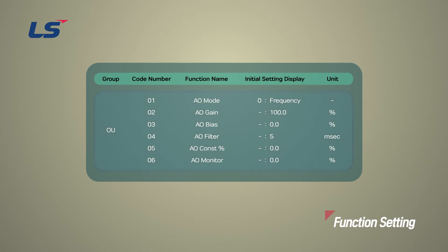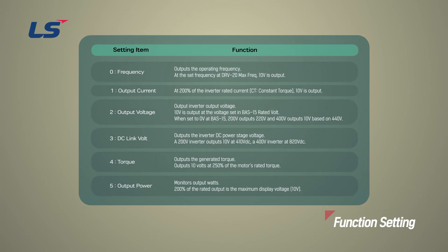Parameters for analog output can be set in the OU group. The AO terminal is a multi-function output terminal. Therefore, you can directly select the output item for AO in OU group 1 parameter. The output items can be selected from the operating frequency shown on the screen to the fixed value output. In this video, we will select the zero operating frequency.